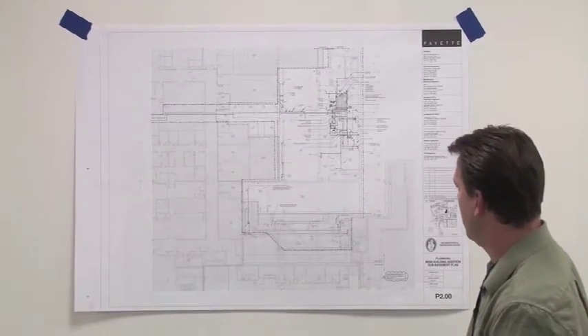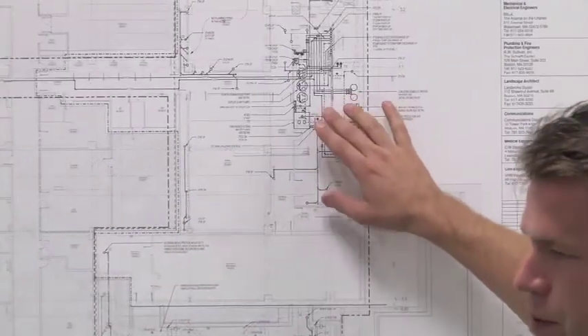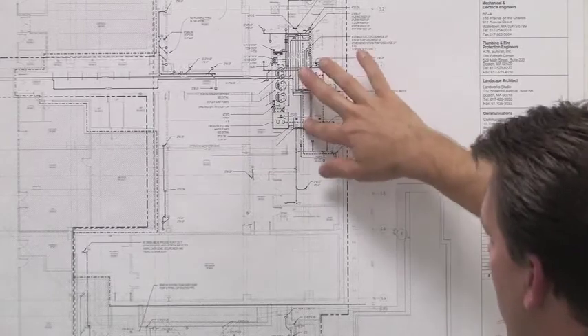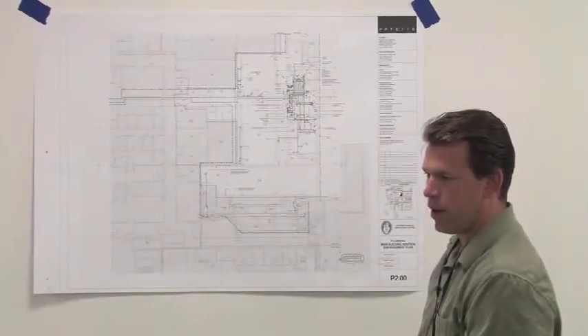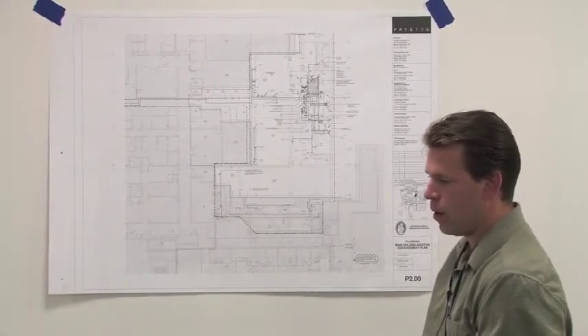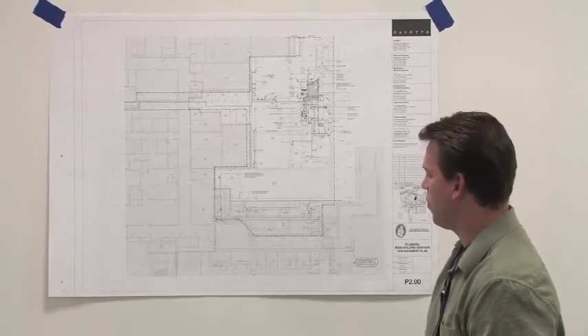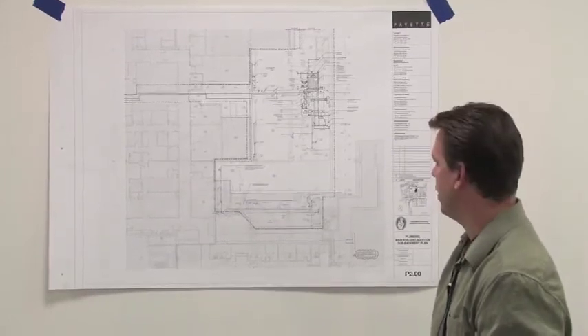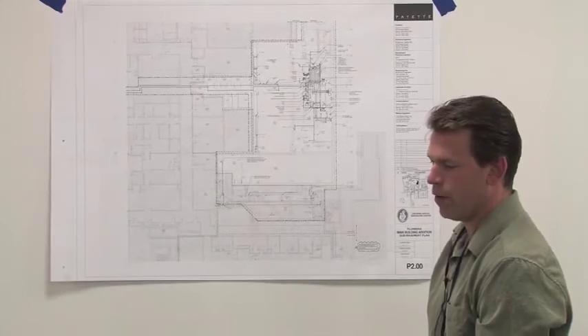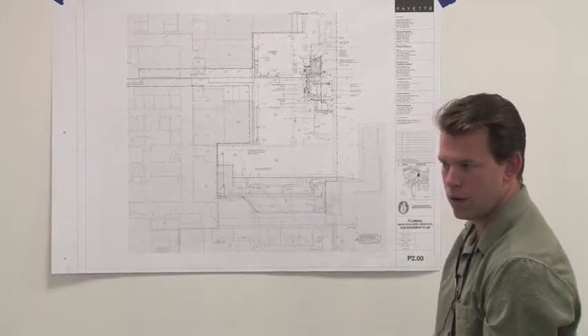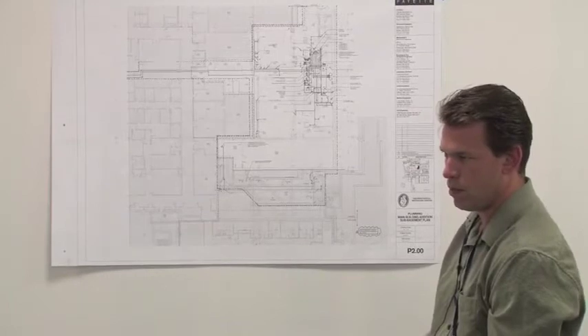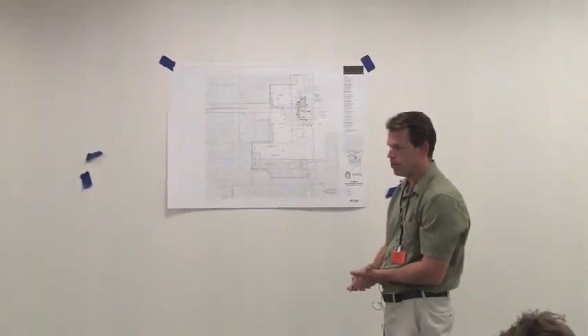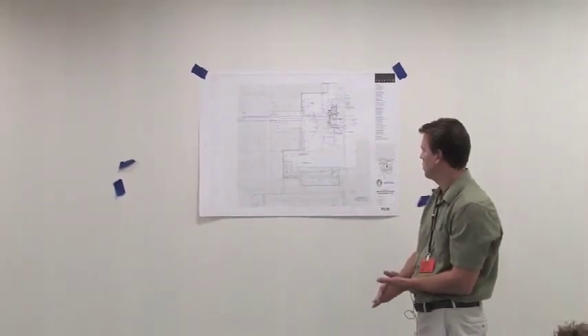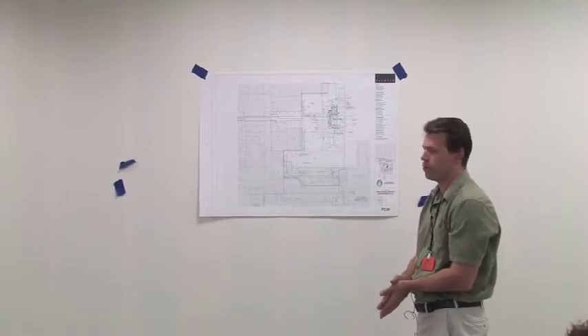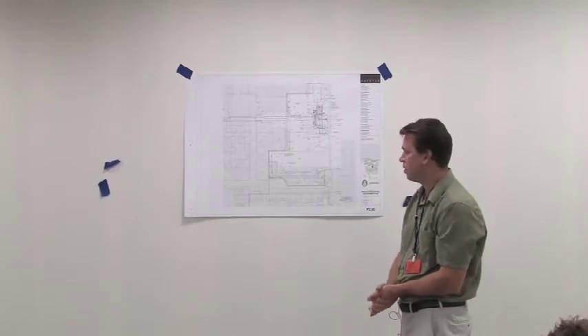Kenny just reminded me that the fire protection water storage tank has a chlorination system located inside this plumbing mechanical room, right on this wall. It simply draws water from the tank, samples it for chlorine content, adds chlorine if it needs it, and pushes it back into the tank. It's programmable to cycle whenever you determine is best, and it monitors and keeps the water free of bacteria. A contractor will be contracted to maintain the skid, but we'll be responding to any alarms that come off for any reason. It's just a glorified large pool filter, because it's 40,000 gallons of stagnant water sitting there, so they're going to treat it and keep it as clean as possible. We don't expect a lot of growth in it. There's no sunlight there, so it should be relatively clean at all times.